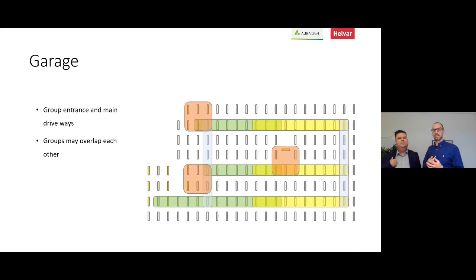So if you start before your group, you go under one luminaire and push the network, then everybody who is in that network will start flashing in 2 minutes. So you can easily go around and see if it's some failure, or can we not get into this area or something. So it's a really good thing just to look that everything is working already. You find all the faults. Yeah, exactly. Something not connected, something broken, the Bluetooth mesh net doesn't reach it or anything. You find it immediately. Yeah.